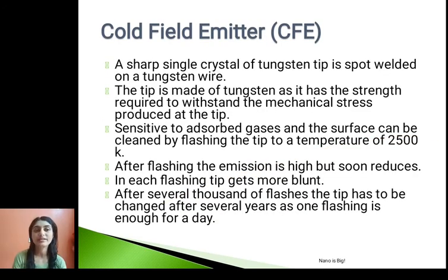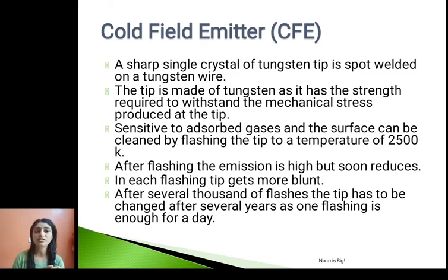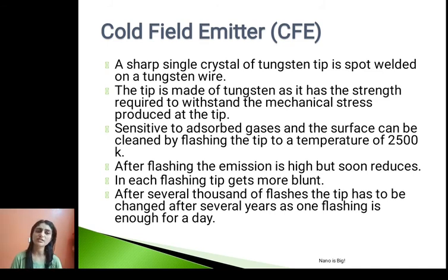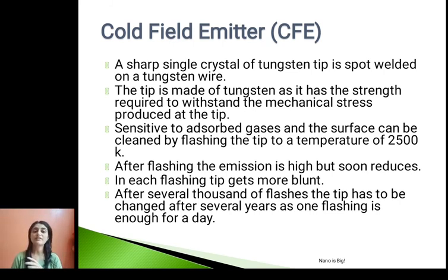In a cold field emitter (CFE), a sharp single crystal tungsten tip is spot-welded on a tungsten wire. Tungsten is used because of its strength to withstand the mechanical stress produced at the tip. It is sensitive to adsorbed gases and the surface can be cleaned by flashing the tip to a temperature of 2,500 Kelvin. Once flashed, emission is high but soon reduces again. Each flashing increases emission but also makes the tip more blunt. After several thousand flashes the tip has to be changed, which happens after several years of usage since one flashing per day is sufficient.